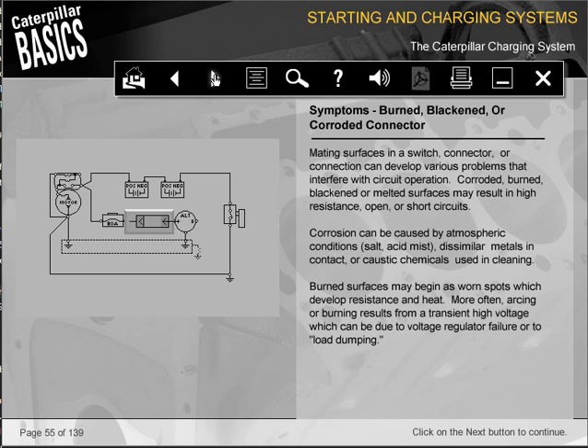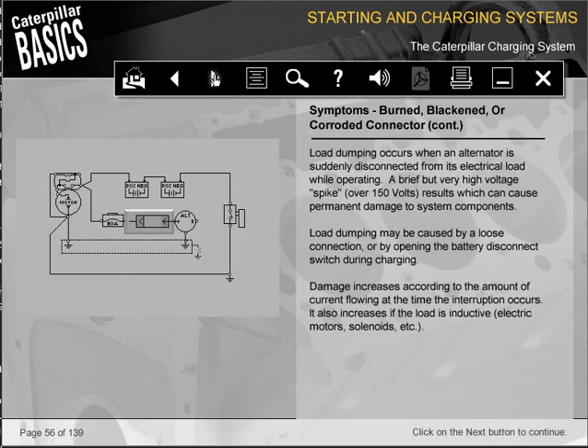More often, arcing or burning results from a transient high voltage, which can be due to voltage regulator failure or to load dumping. Load dumping occurs when an alternator is suddenly disconnected from its electrical load while operating. A brief but very high voltage spike over 150 volts results, which can cause permanent damage to system components. Load dumping may be caused by a loose connection or by opening the battery disconnect switch during charging.